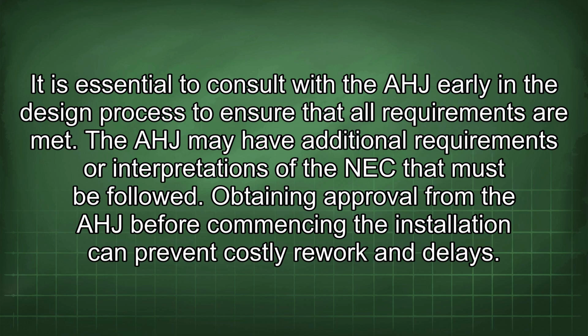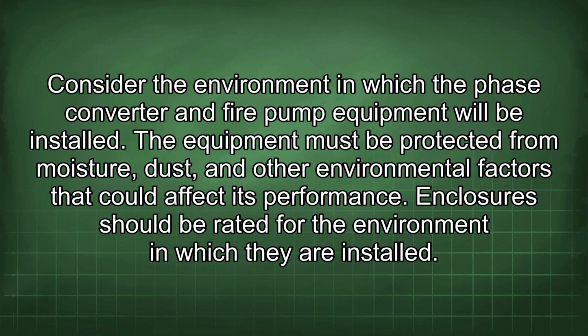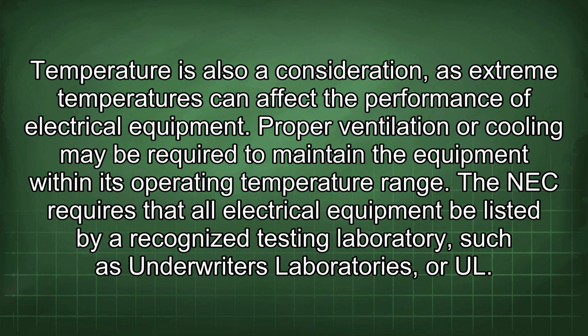Obtaining approval from the AHJ before commencing the installation can prevent costly rework and delays. Consider the environment in which the phase converter and fire pump equipment will be installed. The equipment must be protected from moisture, dust, and other environmental factors that could affect its performance. Enclosures should be rated for the environment in which they are installed. Temperature is also a consideration, as extreme temperatures can affect the performance of electrical equipment. Proper ventilation or cooling may be required to maintain the equipment within its operating temperature range.